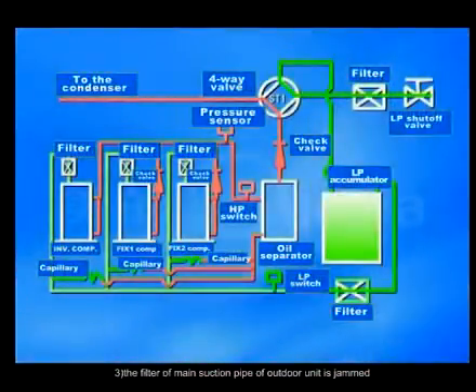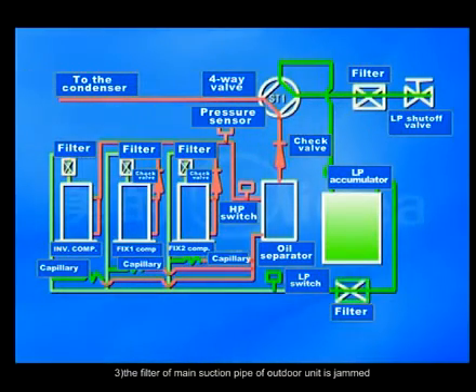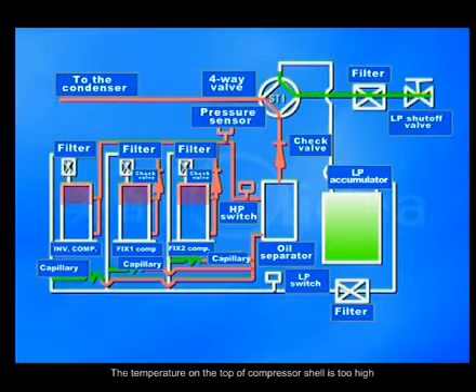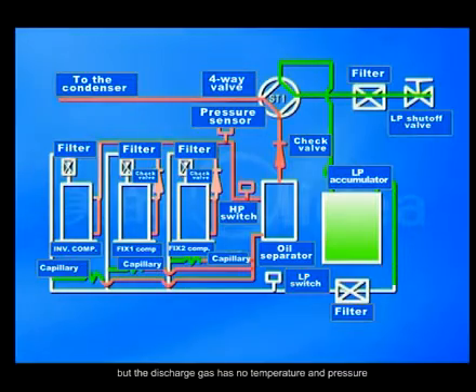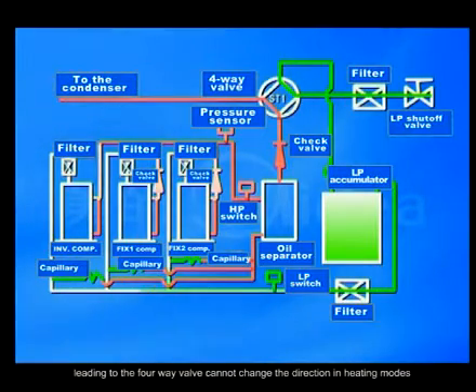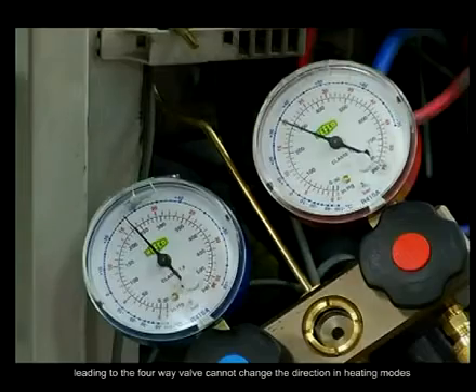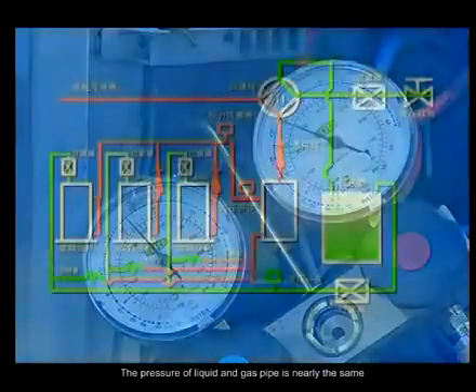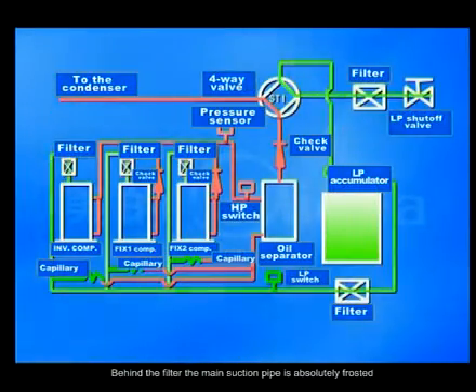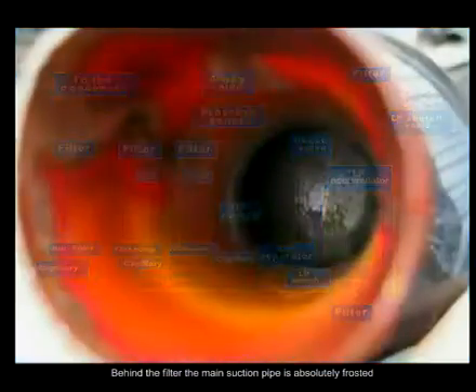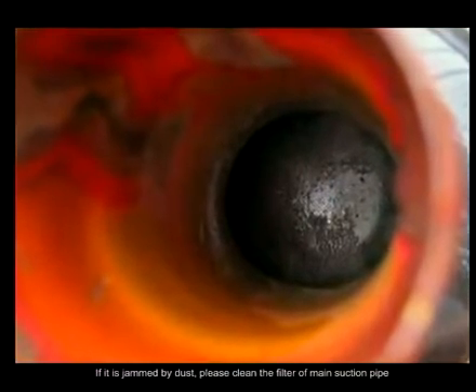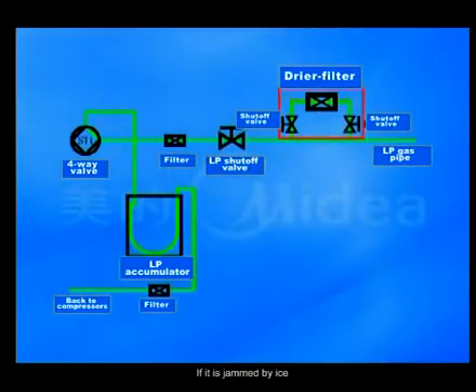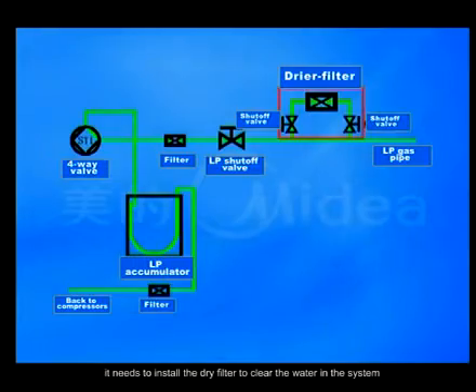Three. The filter of the main suction pipe of the outdoor unit is jammed. The temperature on the top of the compressor shell is too high, but the discharge gas has no temperature and pressure, leading to the 4-way valve being unable to change direction in heating mode. The pressure of gas and liquid pipe is nearly the same. Behind the filter, the main suction pipe is absolutely frosted. Solution. If it is jammed by dust, please clean the filter of the main suction pipe. If it is jammed by ice, you need to install a dry filter to clear the water in the system.